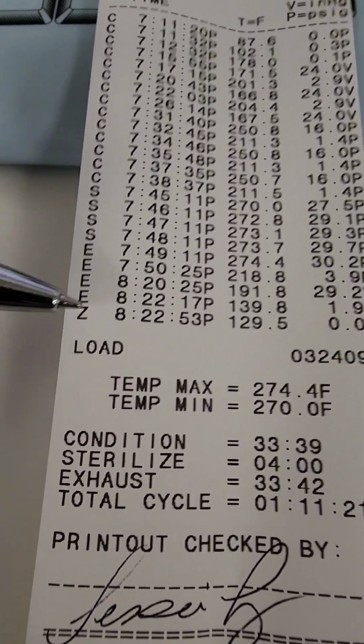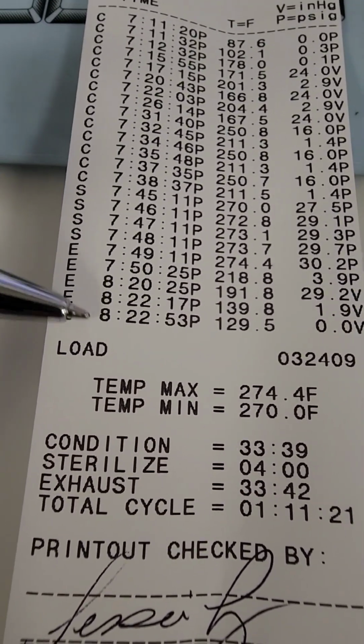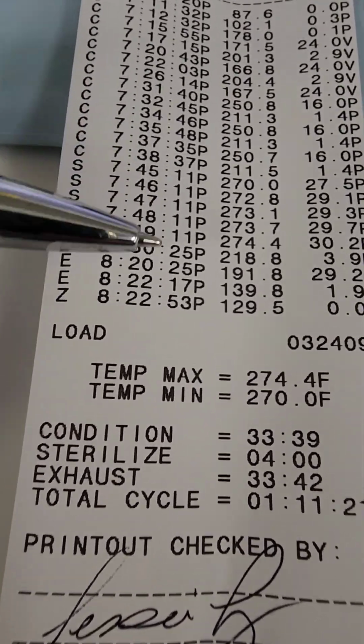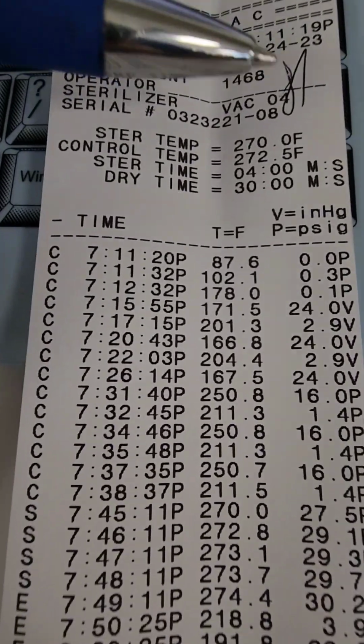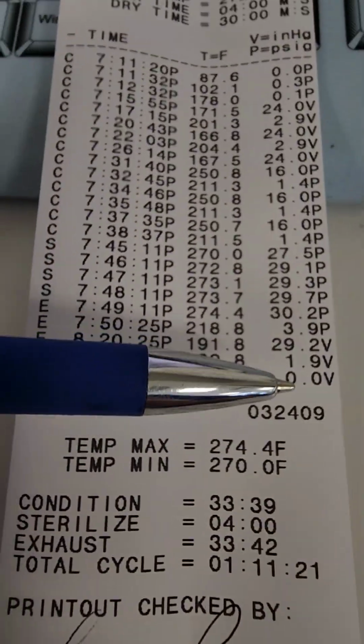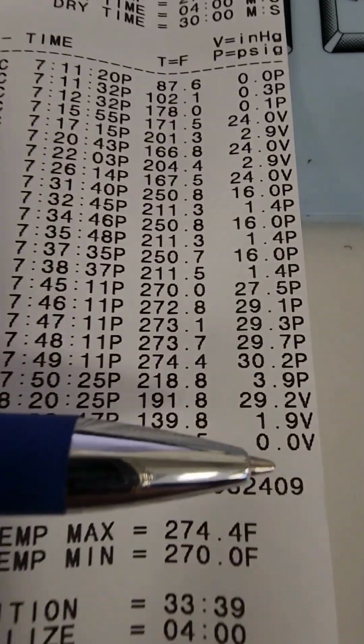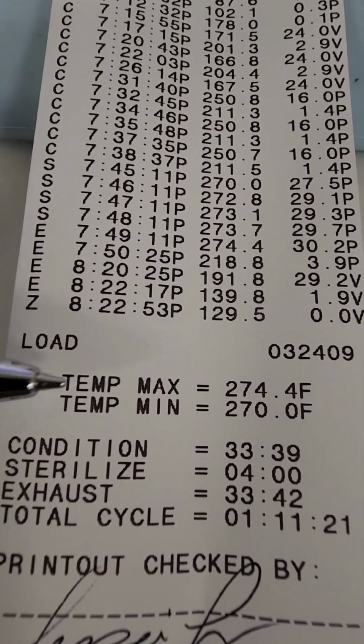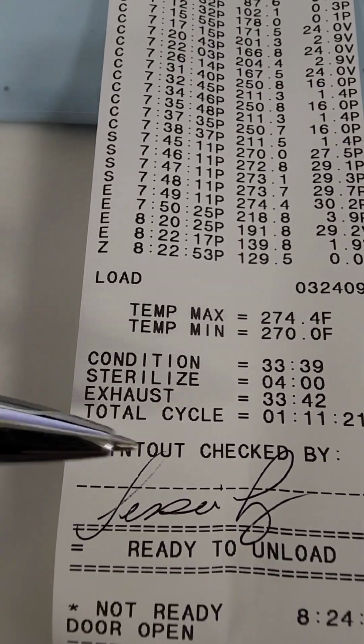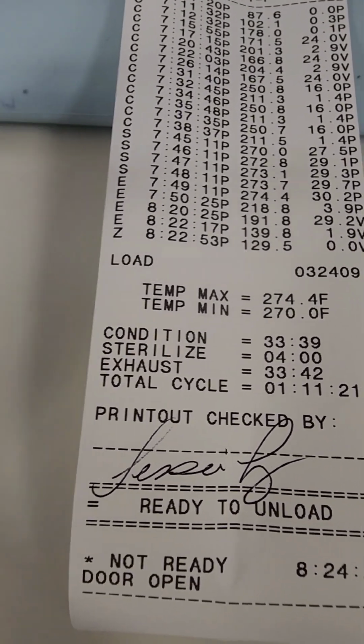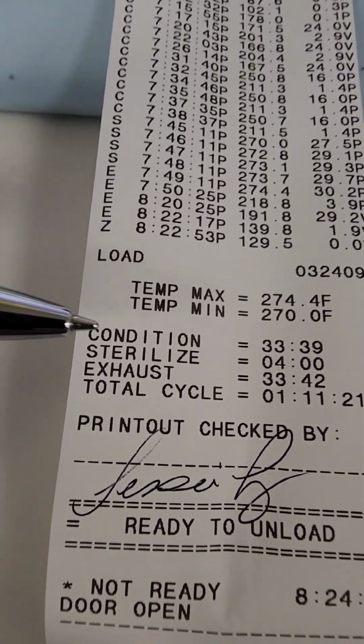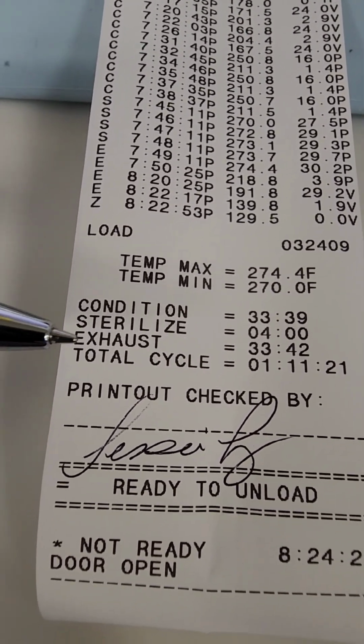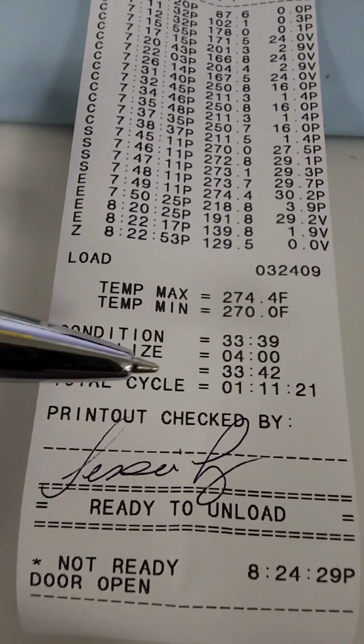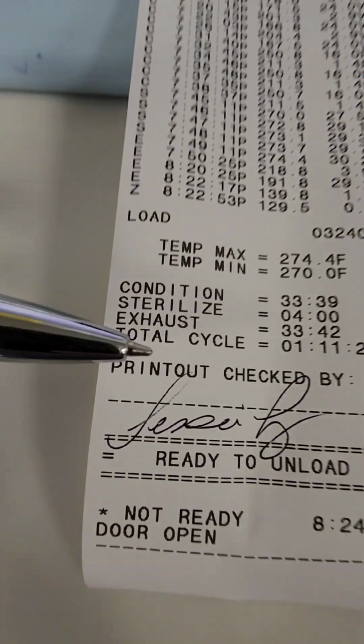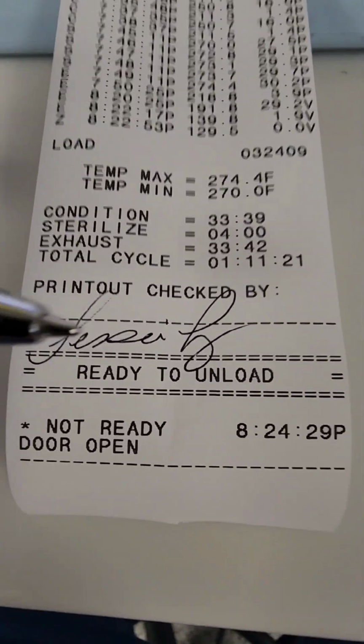Of course, your exhaust and the dry time is never spelled out in time. It just gives you that Z, and that's where your dry time starts. Again, you look at your sterilizer name and what load it was. So this was sterilizer number 4, load number 9, because of the last number in that load. It tells you what was the maximum temperature read and the minimum temperature that it started at. Your conditioning time, your sterilization time, your exhaust, and total time of the cycle. Again, these numbers can fluctuate, but your sterilization time should not. And end with a signature.